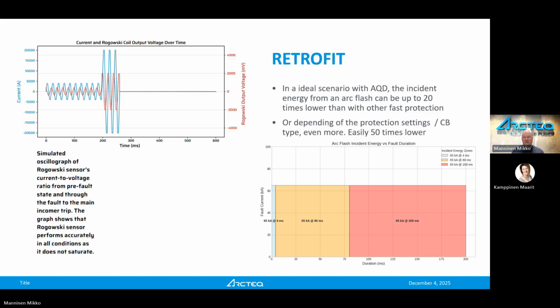And this area here is then the arc flash incident energy. And with arc flash protection, we can then limit it to here, which is already a lot better compared to this red one. And with arc quenching and arc mitigation systems, we can go to here. And this is very self-explanatory, that we can have even 20 times less, or even much more if we compare this whole area. So even 50 times lower values. And all according to standards and these calculation standards, this all has a huge impact and effect on what to wear on site, what kind of PPE, what categories we are in, and so on.